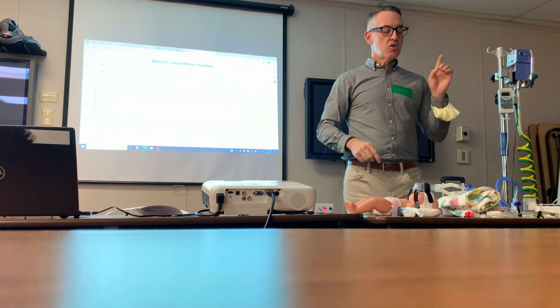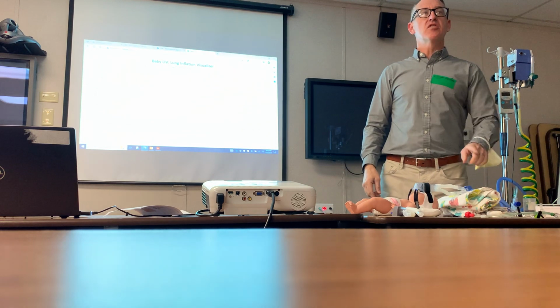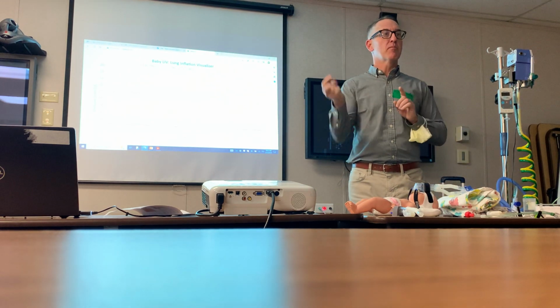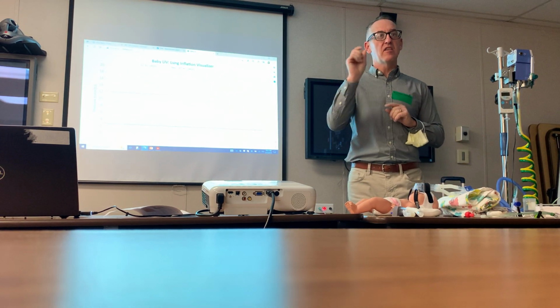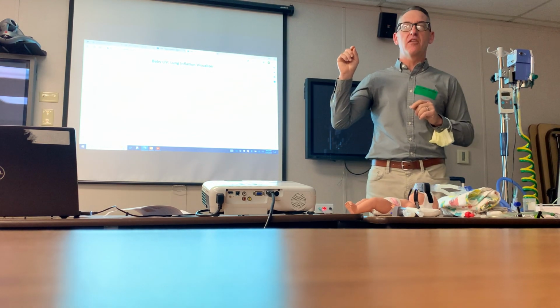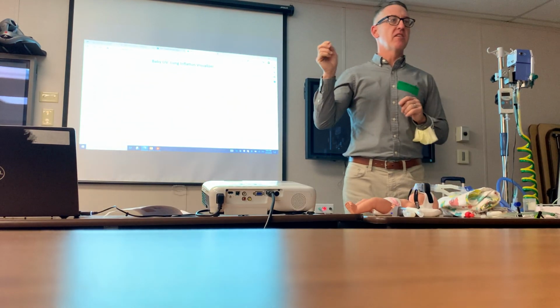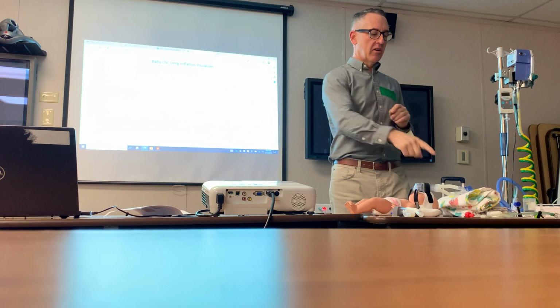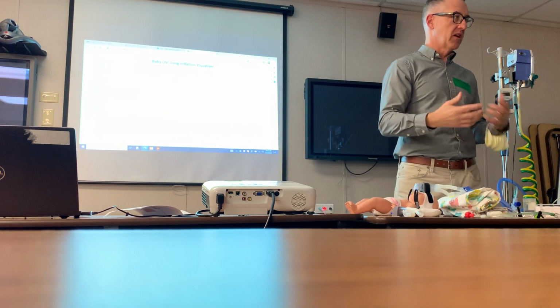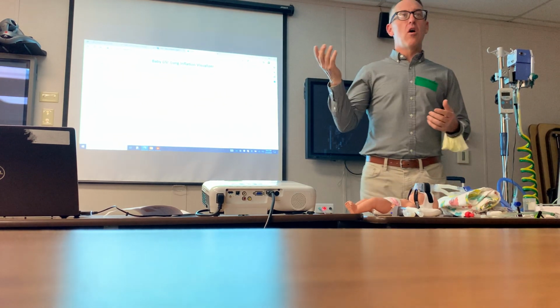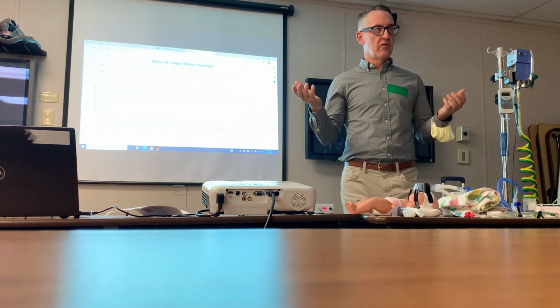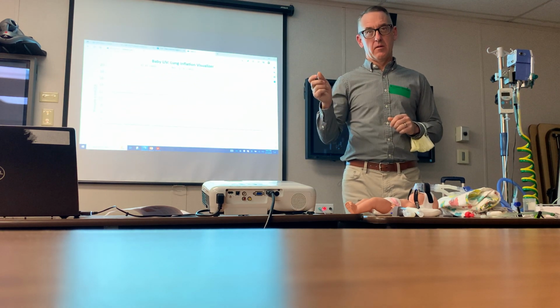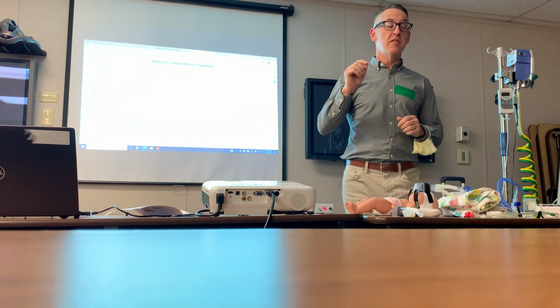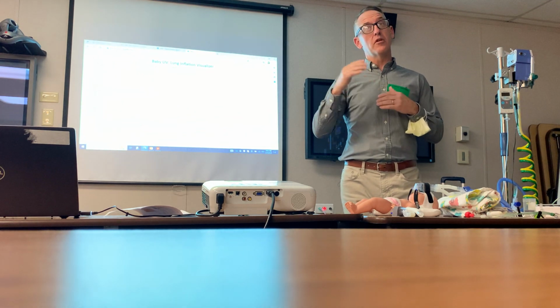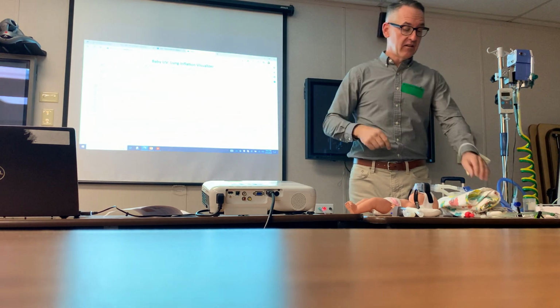Why? When these first came out, the recommendation from Fisher and Paykel was to have the temperature probe outside of the incubator, because incubator settings used to always be set at manual mode at about 36 to 37 degrees Celsius. That would cause haywire with the temperature probe, and you'd get tons of rain out. Now with all of these awesome incubators that you guys have, everybody uses baby mode, and the temperature within that incubator typically doesn't go above 32, 33 degrees Celsius, and it doesn't cause haywire with the temperature probe.